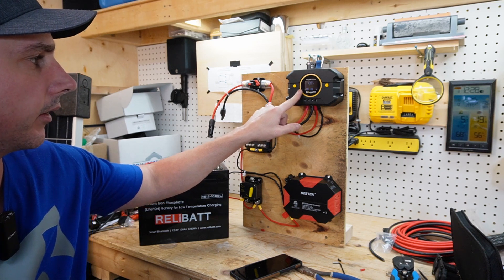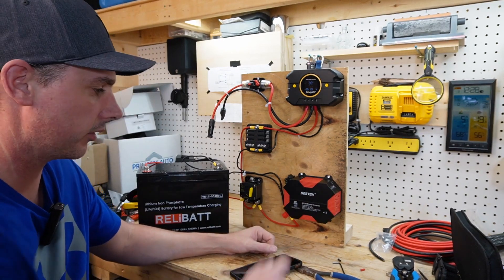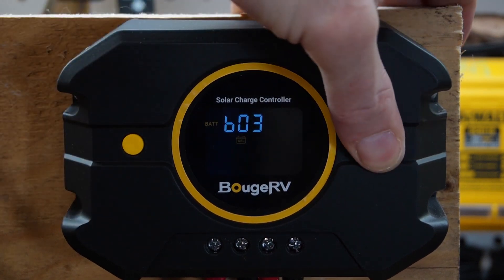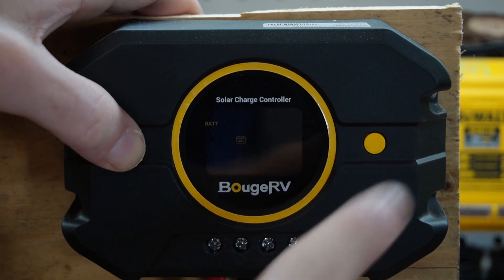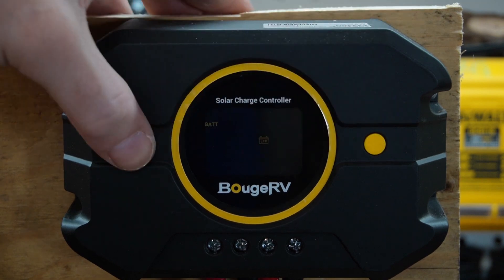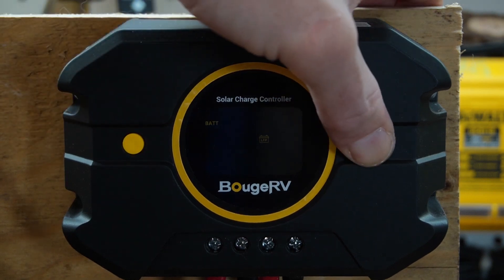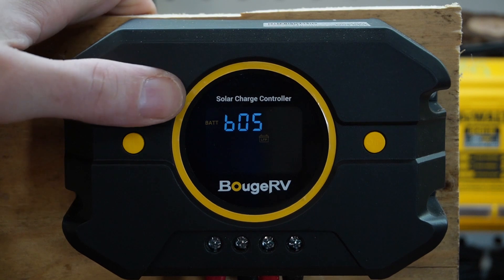And straight away we can see that the BougeRV charge controller has come on, and we also have power to our inverter. Now looking at the charge controller, you can see the battery setting is B3, which is gel — we want to change that to B5. And there you can see B5 is now selected. We are set to battery type B5, which is lithium iron phosphate.